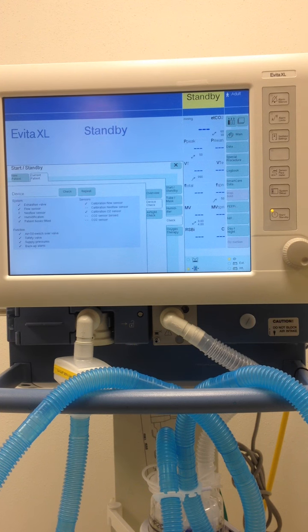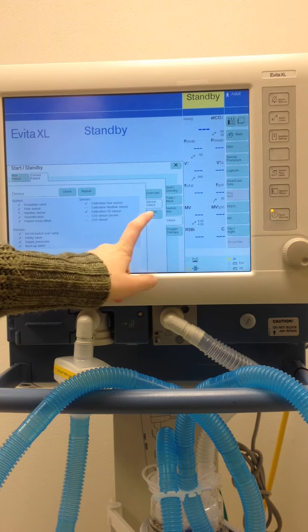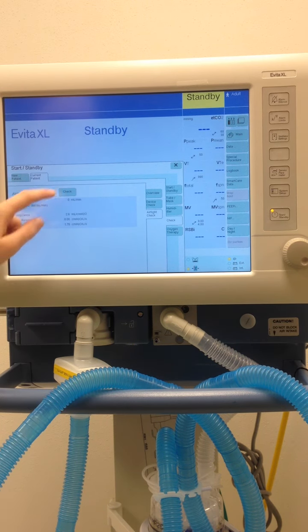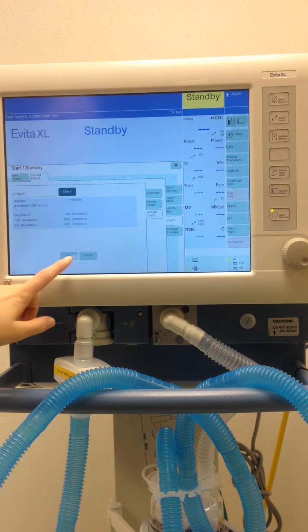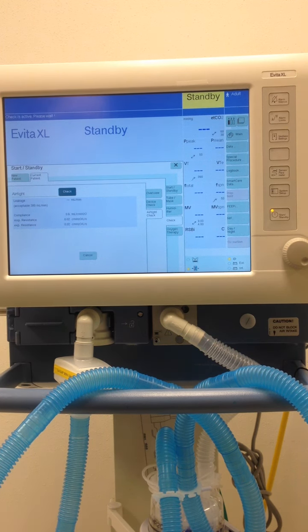And then our test is completed, so we can see we failed the NeoFlow sensor. That's okay, we're not using that. Everything else has checks, except for what we skipped. So we are good on our device check. Now our airtight check, we can just click check. It says seal your Y piece and confirm with yes. It's going to check your circuit for any leaks.